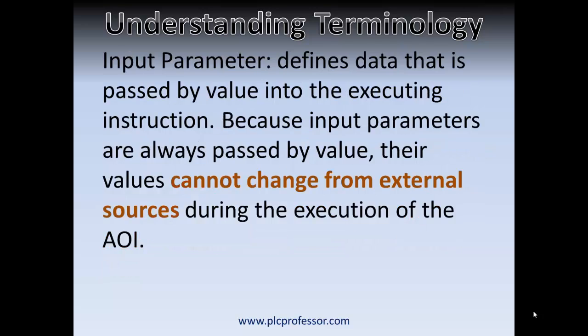The other form we have is an input parameter. This defines data that is passed by value into the executing instruction. Because input parameters are always passed by value, their values cannot change from external sources during the execution of the code. Whereas in-out parameters referred to a tag out in the general tag population, this type of parameter reads the tag or value at the beginning of execution and it does not change during execution. The value is passed in from that tag and then accessed during the execution of the code in the add-on instruction. Once it's passed in by value, that value is used throughout execution.